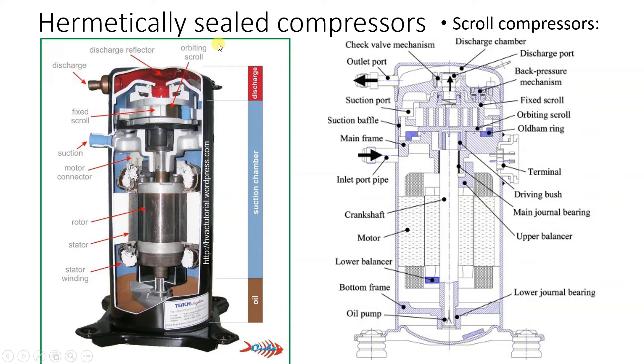Next compressor is hermetically sealed scroll compressor. This compressor is usually taller compared to reciprocating compressor. The bottom side has oil, the middle part is the suction chamber, and the top red-colored part is the discharge chamber. At the bottom there is an oil pickup tube, stator, and rotor. Then there is the crankshaft, and we have two scrolls: one fixed scroll and one orbiting scroll. Below the orbiting scroll there is the Oldham ring.